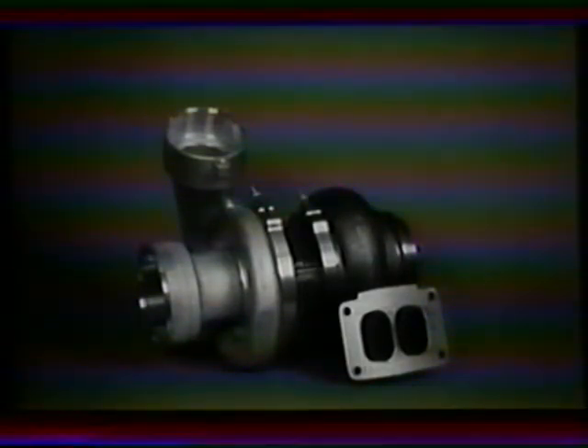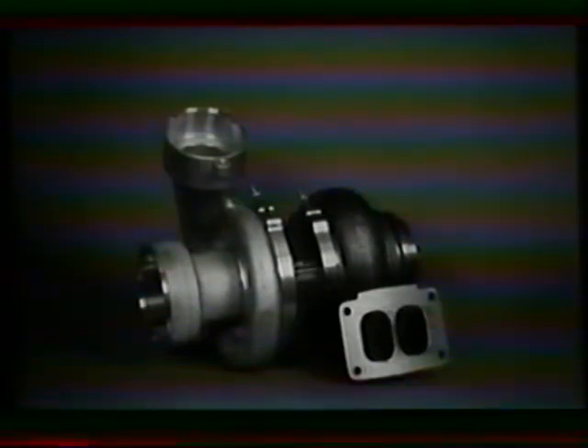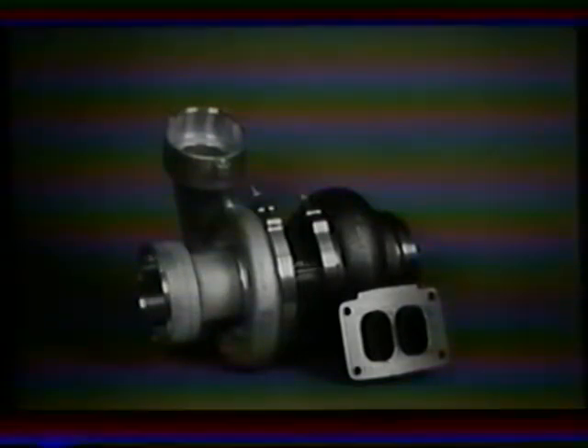Also, the turbocharger compensates to maintain combustion air density as altitude increases. Turbocharged 3300 series engines operate at higher altitudes before derating, compared to naturally aspirated engines. The low inertia turbocharger wheel provides fast response to load changes or accelerator demand.